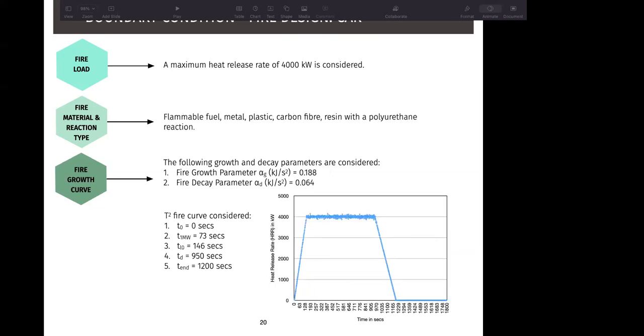Similarly, if we look at a car on fire, we can have this same sort of fire curve where a maximum heat release rate of 4000 kilowatt is considered, which is 4 megawatt. This is for a car with fuel. The fire material considered is flammable fuel, metal, plastic, carbon fiber, resin with polyurethane reaction. In this case, the growth rate is considered as a fast growth rate of 0.188, and decay rate is considered as 0.064, which dictates that the peak fire load will be reached at 146 seconds, and it will start to decay at 950 seconds for a 20-minute fire.